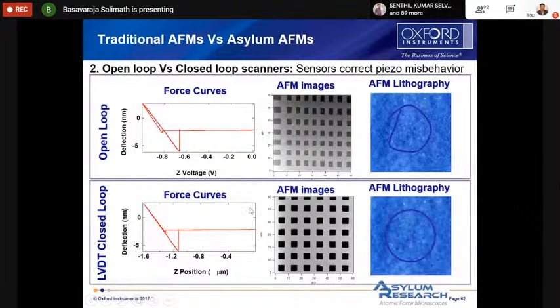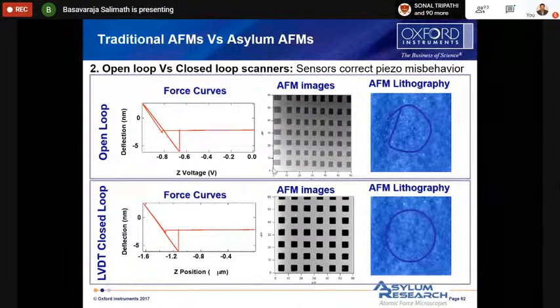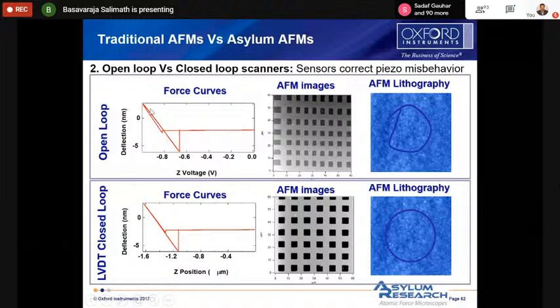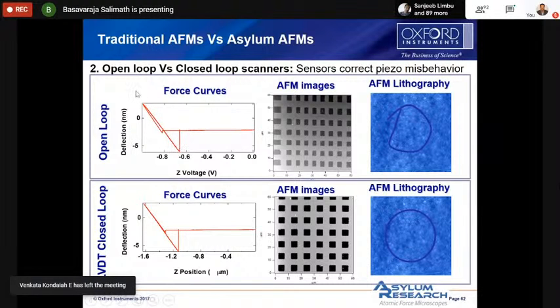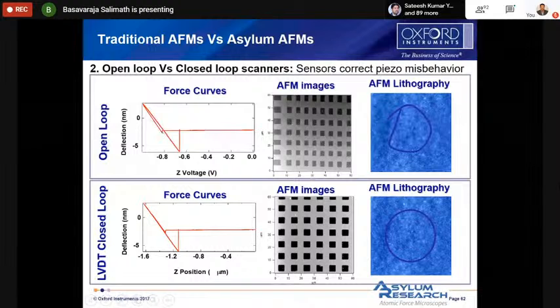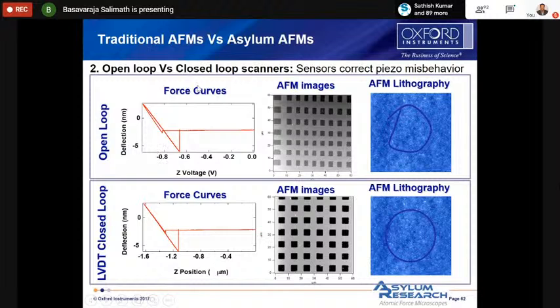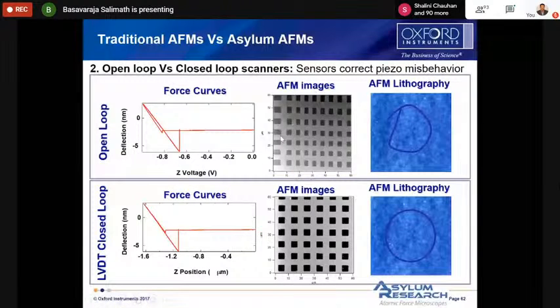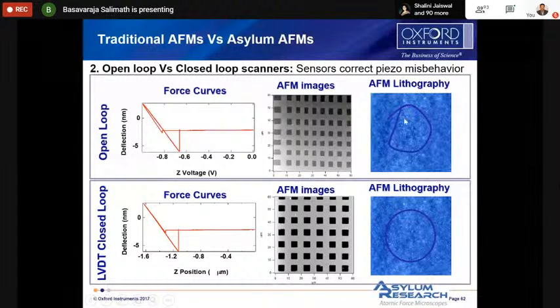Also, all these scanners are made up of piezoelectric materials, and piezoelectric materials have hysteresis. Hysteresis means that if you apply some voltage, initially it may go like this, but when it comes back it takes a different path, though it should come back on the same path. That is called hysteresis, and it is there in all piezoelectric materials. Because of that, if you are doing FD curves, you get differences. You can see that at the center it will be nice, but at the ends your images will be stretched. And if you are doing lithography and draw a circle, you will not get a circle.